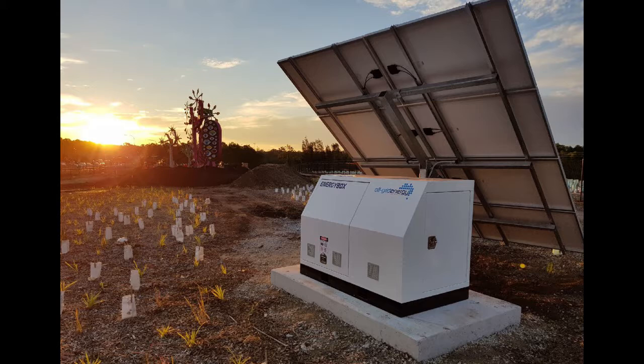This is one of our little energy box designs. In this case it's a gen-free system. We don't normally recommend off-grid systems without generators, but this was an unmanned site where it wasn't possible to have a generator. Really, you just have to oversize the solar and make sure the battery capacity is large enough to get you through the worst case scenario, which is usually around the shortest day of the year, give or take a month, when generators tend to get used.